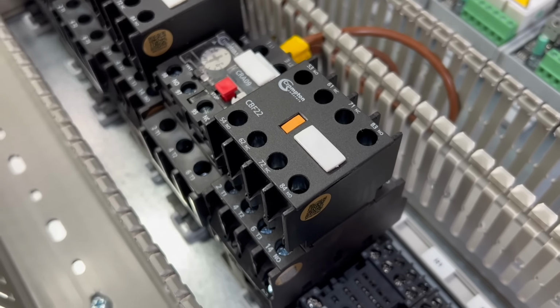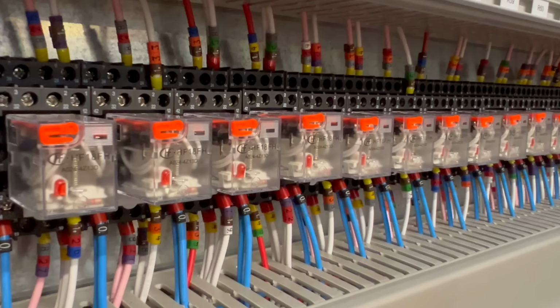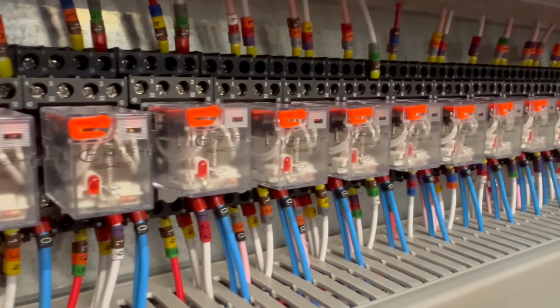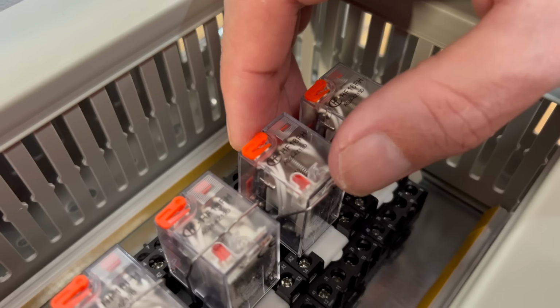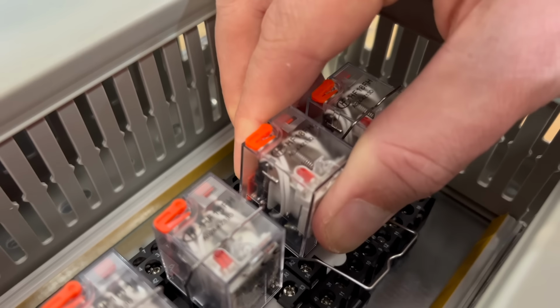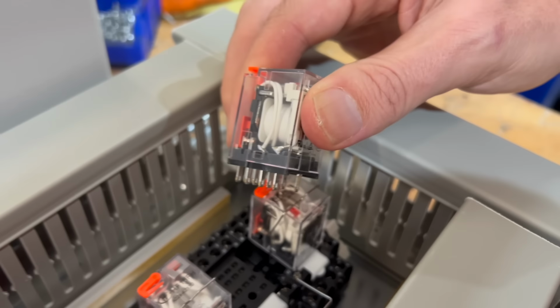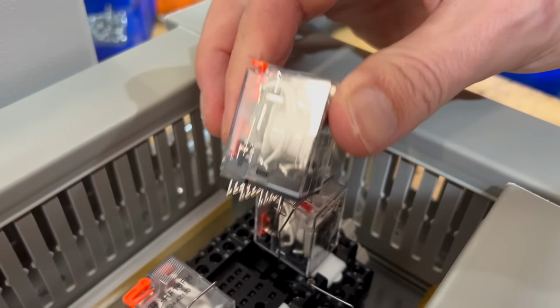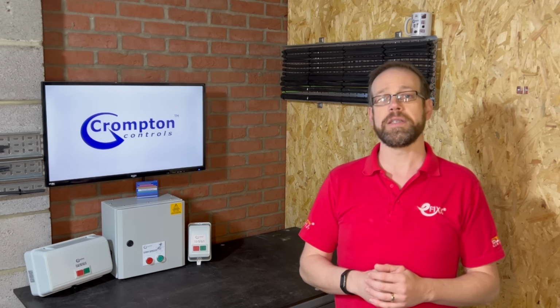and control. While we're on the subject of switching loads, you may also come across a similar device that looks like this. This is a relay, which does pretty much the same thing as a contactor, but with a lower current rating on the switching terminals. The relay can be removed and replaced simply by pulling them out of the hardwired base they plug into, making maintenance really easy. You may also come across a couple of other devices in a control panel.